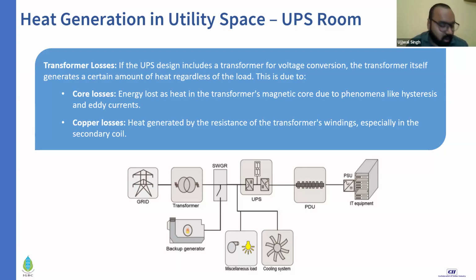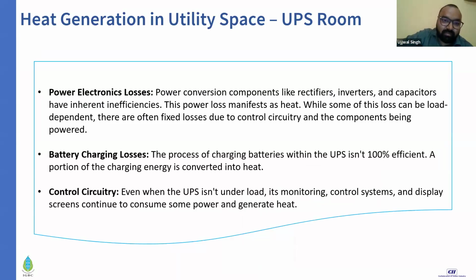For the non-electrical people, transformers generally have two kinds of losses. One is core loss and the other is copper loss. Core loss is defined by the amount of hysteresis and eddy currents generated in the magnetic core. And copper loss, as you are aware, is due to the resistance in the secondary coil because of the voltage conversion.